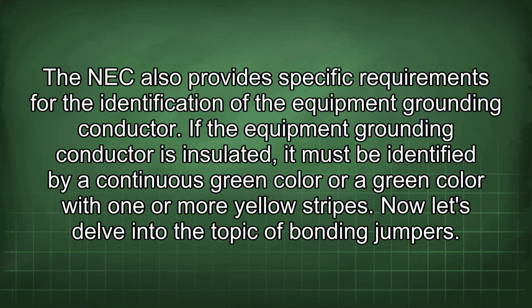The NEC also provides specific requirements for the identification of the equipment grounding conductor. If the equipment grounding conductor is insulated, it must be identified by a continuous green color or a green color with one or more yellow stripes.